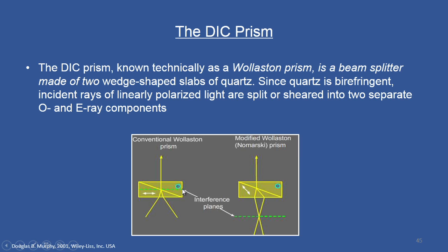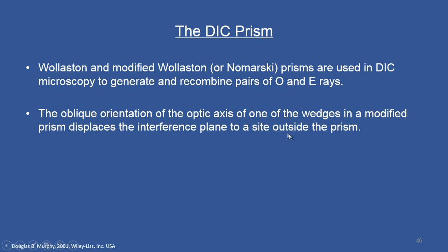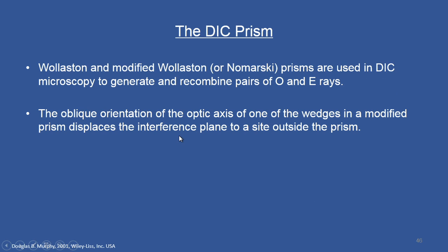The modified Wollaston prism, or Nomarski prism, also has two wedge-shaped slabs, but their orientation is slightly oblique. As a consequence of the oblique orientation, the interference plane is shifted out of the prism. This is what distinguishes the Nomarski prism from the conventional Wollaston prism. The oblique orientation of the optic axis of one wedge in the modified prism displaces the interference plane to a site outside the prism.